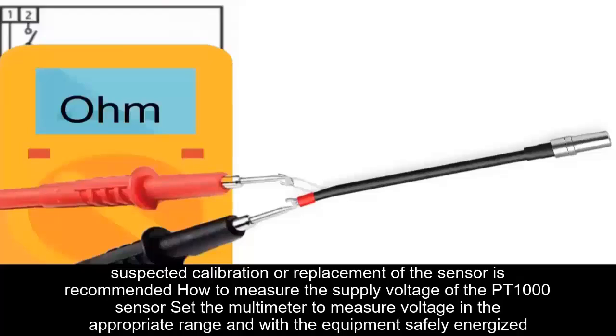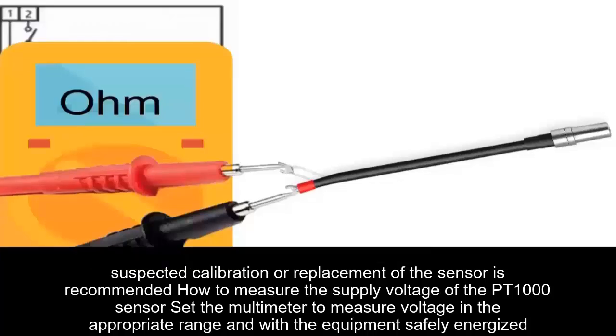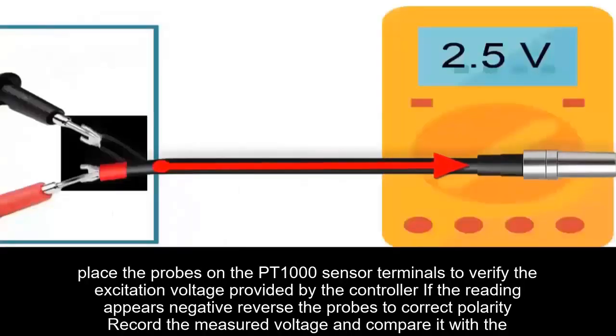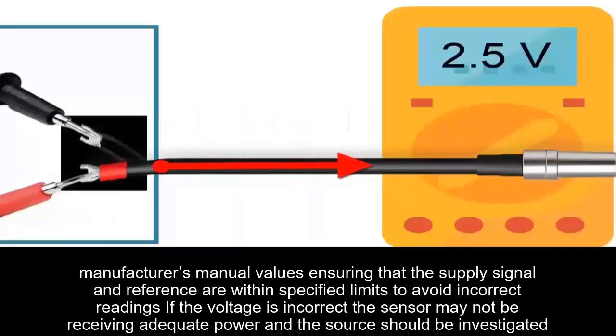How to measure the supply voltage of the PT1000 sensor. Set the multimeter to measure voltage in the appropriate range, and with the equipment safely energized, place the probes on the PT1000 sensor terminals to verify the excitation voltage provided by the controller. If the reading appears negative, reverse the probes to correct polarity. Record the measured voltage and compare it with the manufacturer's manual values, ensuring that the supply signal and reference are within specified limits to avoid incorrect readings.